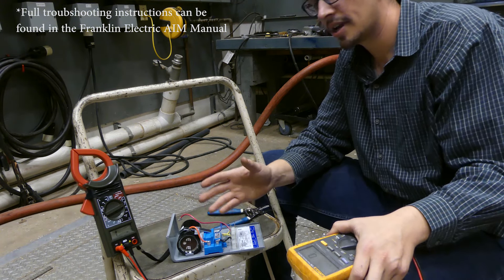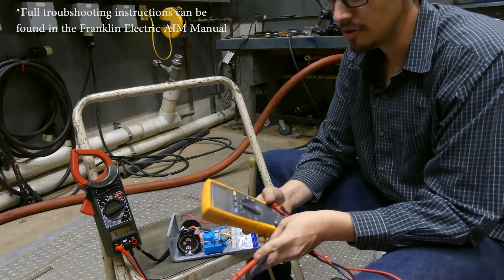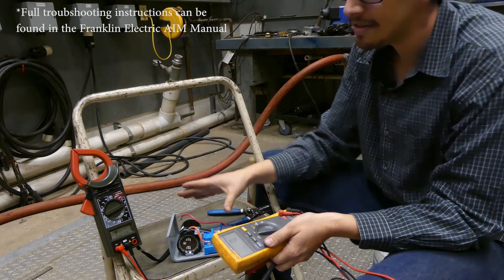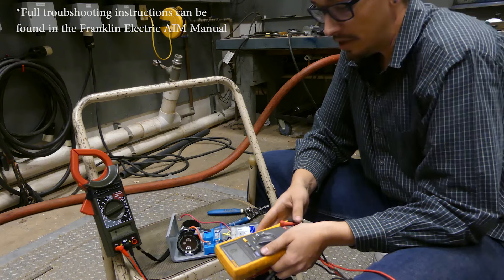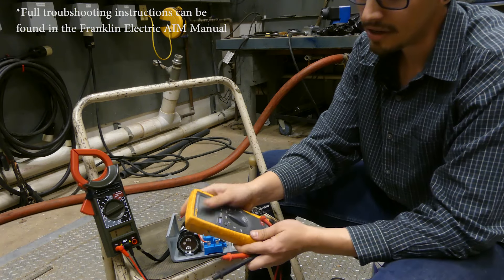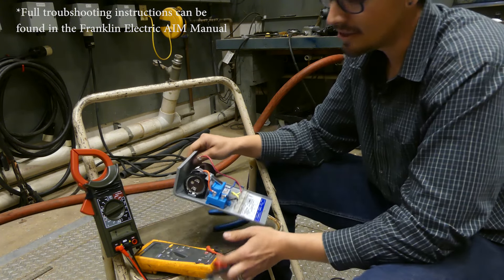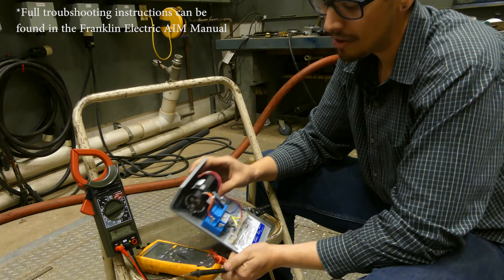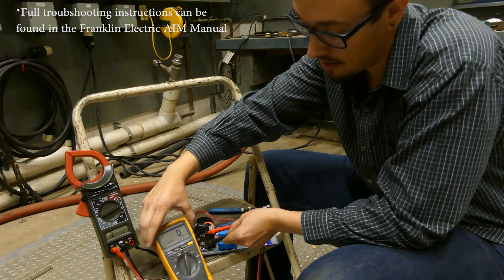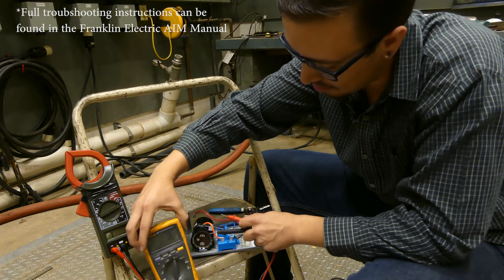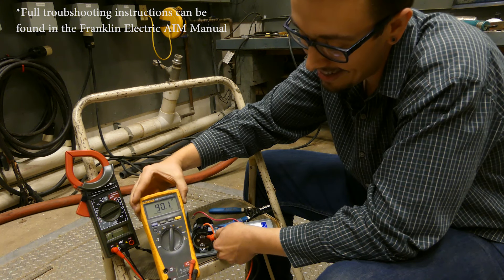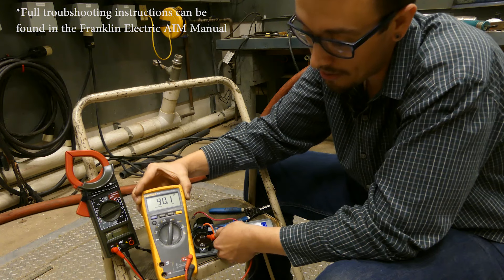One thing I wanted to point out: we've avoided using more expensive meters like Fluke meters just because I wanted to show people on a budget how they can troubleshoot their system. But there is a secondary test you can do that is out of the range of this particular meter—testing the microfarad rating of the capacitor itself. This Fluke meter has the ability to test microfarads. The microfarad rating in this capacitor is written on the side here, between 86 and 103. When we put the meter on at that rating, we're supposed to be between 86 and 103. In an ideal situation, you're somewhere in the middle. I would say we're in pretty good shape.